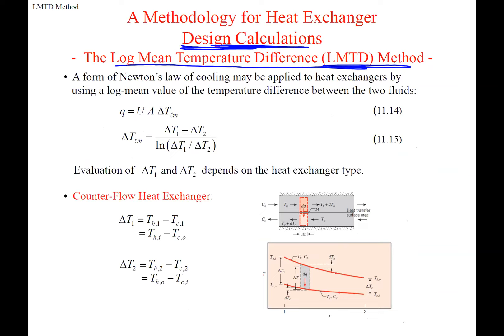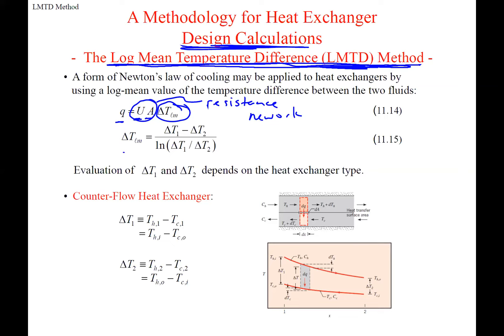Now getting into design calculations using the log mean temperature difference (LMTD) method. This was introduced in Chapter 8 and uses the overall heat transfer coefficient times surface area. The total heat transferred equals UA times the log mean temperature difference. Delta T1 and delta T2 are defined differently depending on the heat exchanger type.